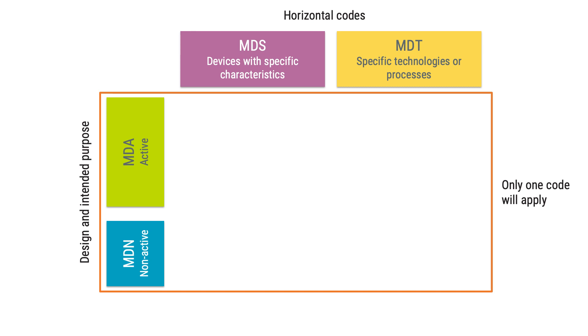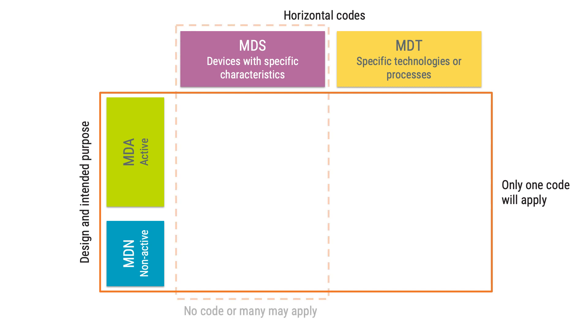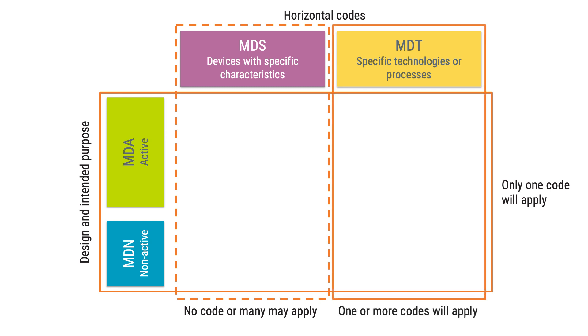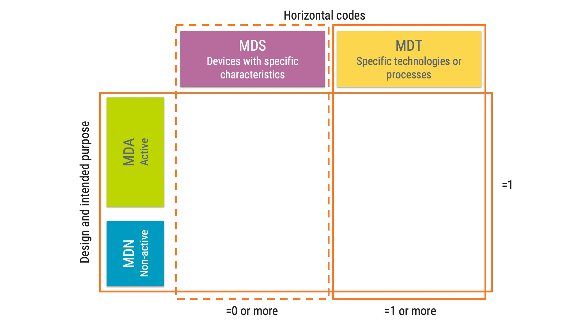When it comes to MDA and MDN codes, the manufacturer and the notified body need to agree on one applicable product code for each device. For the MDS specific characteristics codes, it could be that no code applies, or that several codes apply, depending on the characteristics of the device. For the MDT technology codes, you need to specify at least one code, but there could also be several applicable codes. When a manufacturer applies to a notified body, they need to specify which of these codes applies to each of their devices, so that the notified body can decide if they are designated to work with those devices.